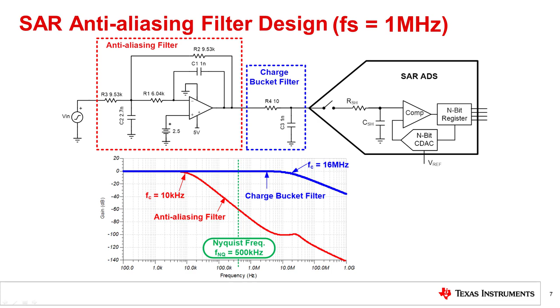In this example, the anti-aliasing filter is an active, second-order low-pass filter with a cutoff frequency of 10 kHz. This filter has an attenuation of 60 dB at the Nyquist frequency, so it functions as an effective anti-aliasing filter. An important point to make here is that the SAR typically does not have an integrated digital filter, so an external active filter that has significant attenuation at the Nyquist frequency is required to prevent aliasing. The delta sigma converter, on the other hand, always has an integrated digital filter, so the anti-aliasing requirements are significantly relaxed.